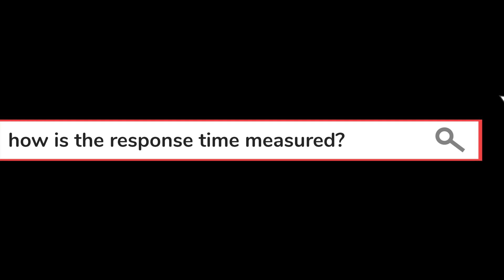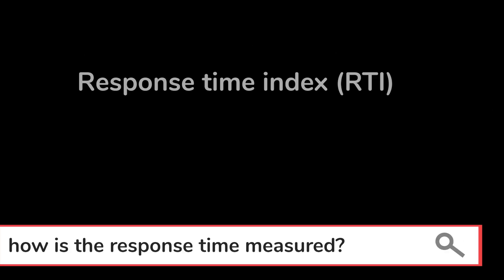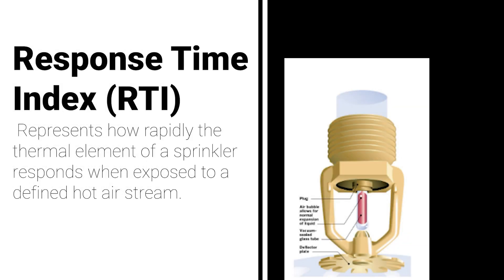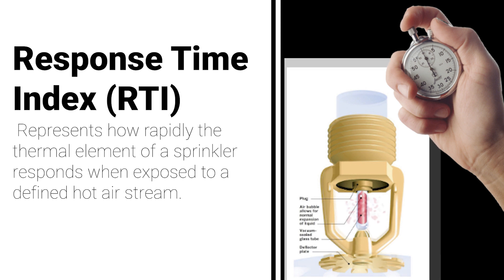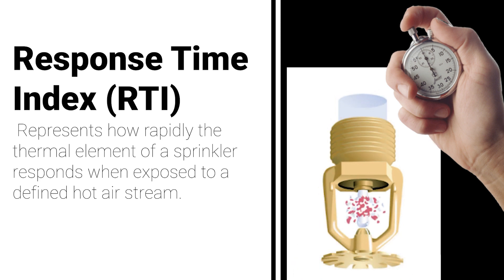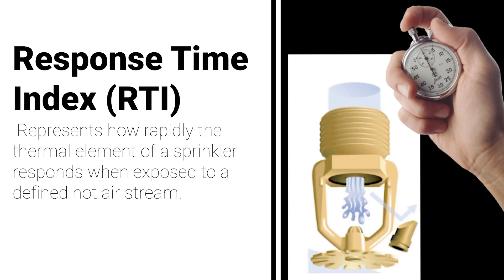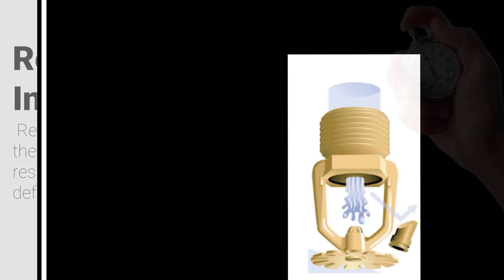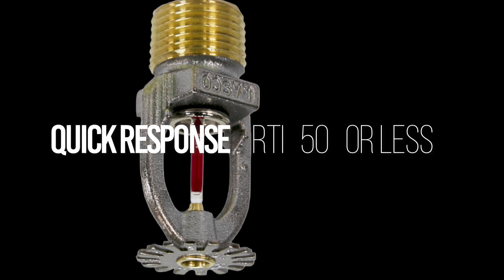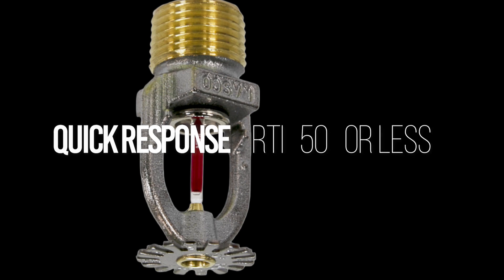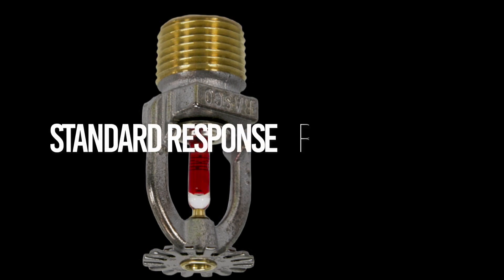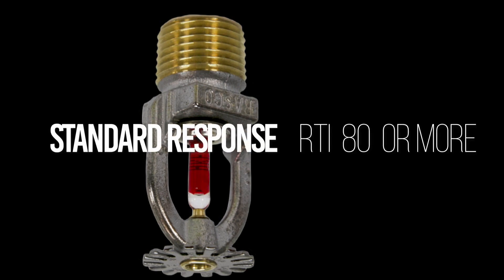How is the response time measured? Response Time Index — RTI. The response time index represents how rapidly the thermal element of a sprinkler responds when exposed to a defined hot airstream. The quick response RTI is 50 or less, and the standard response RTI is 80 or more.